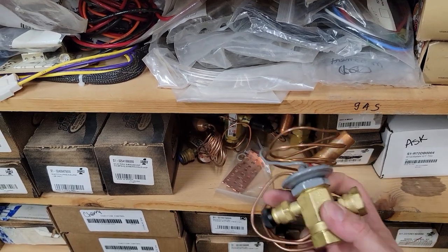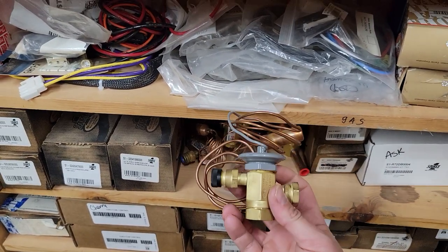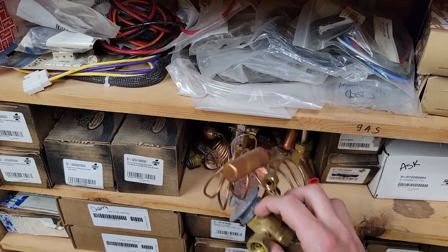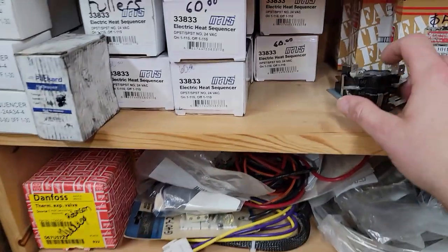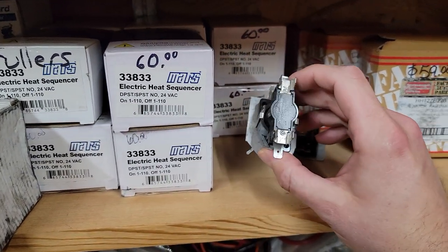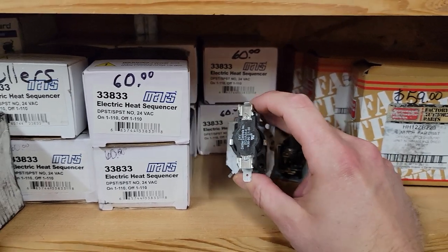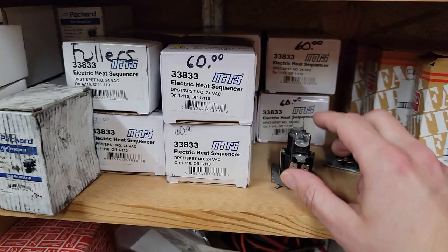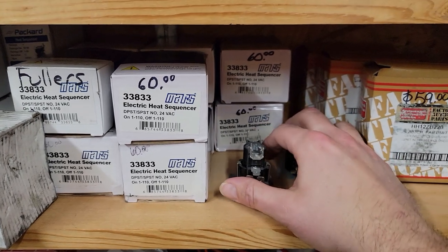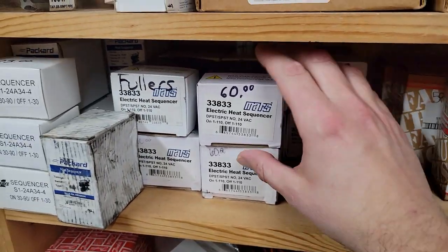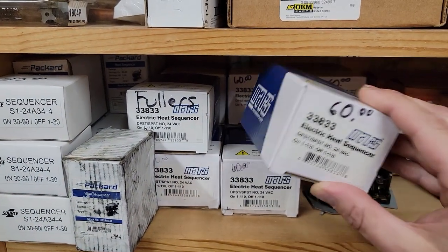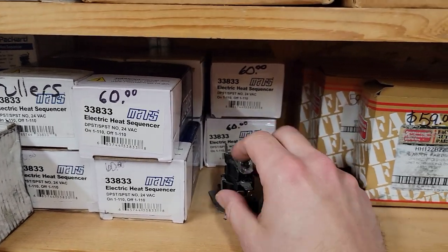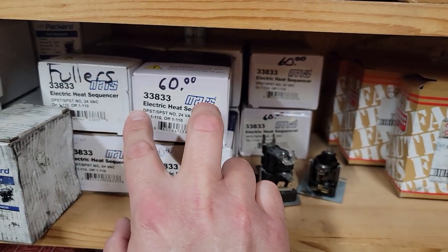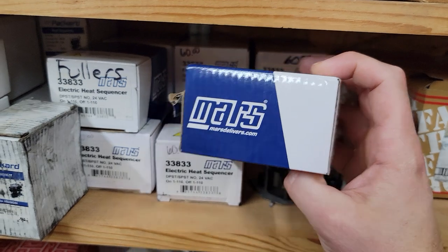Usually you don't carry TXVs with you. Usually you get them all on the serial number and you order if the metering device is bad. This is sequencer's. Number one part that goes bad on trailer furnaces is a sequencer. Change it wire for wire unless all the wires are burned up. Then you may need to do some rewiring. But this is a double pole sequencer, okay? And this is a single sequencer. I mean, not double pole sequencer. These are double sequencers. There's two sequencers in here, right?